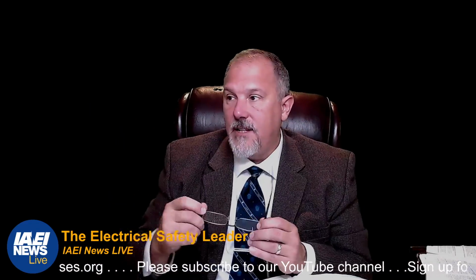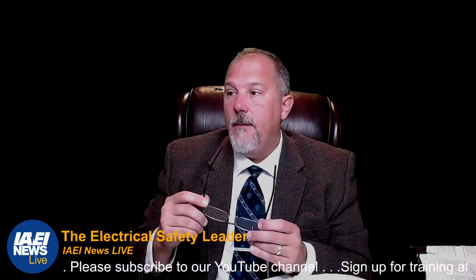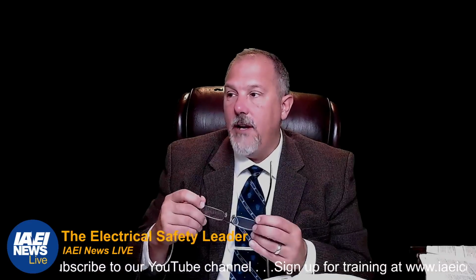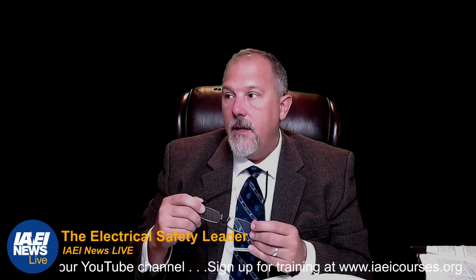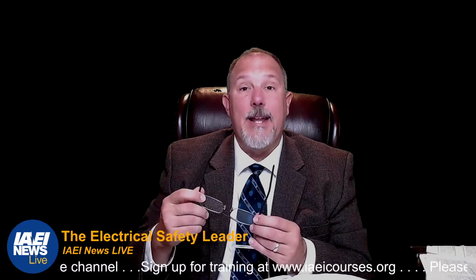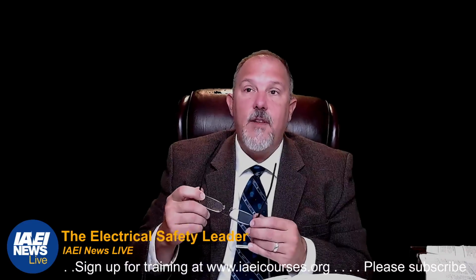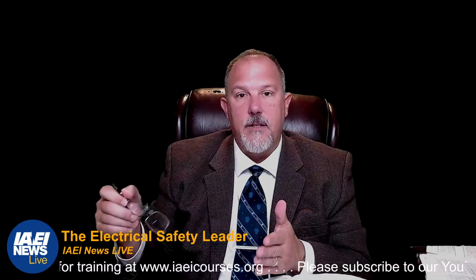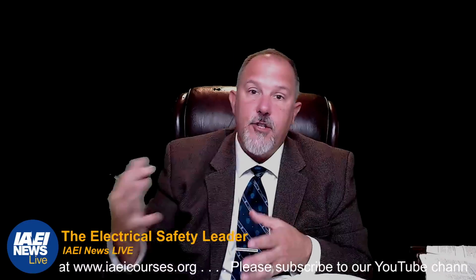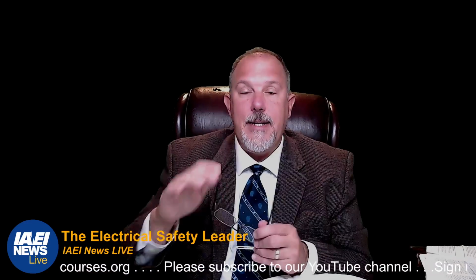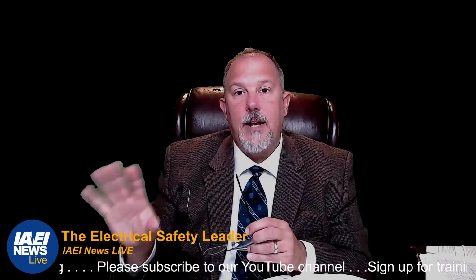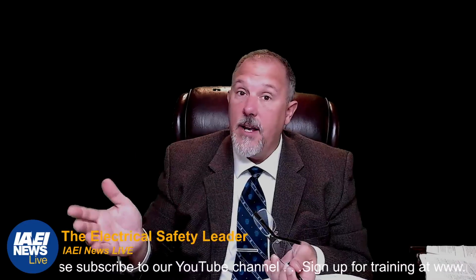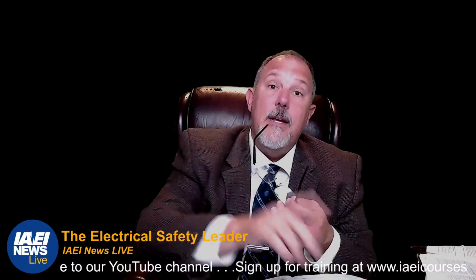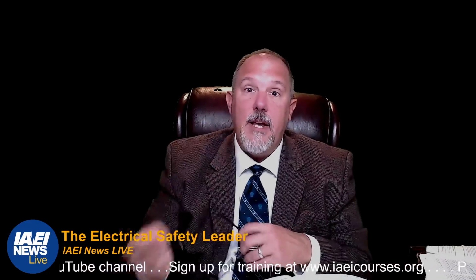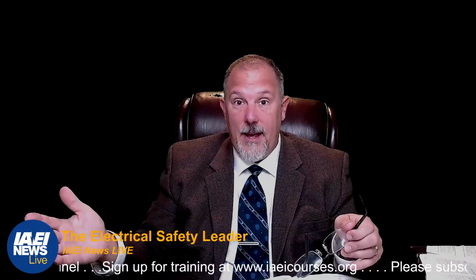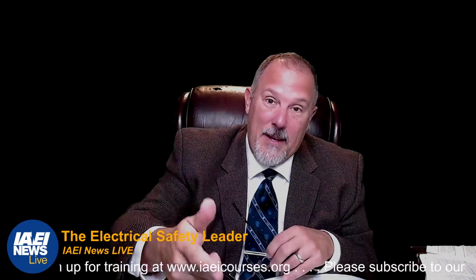Panel boards not listed for the specific enclosure: if the available fault current is greater than 10,000 amps, the completed work shall be field labeled. So what you'll have to do, if the available fault current is greater than 10,000 amps, and you're going to use a retrofit interior, then you're going to need to get an AHJ out there, or a field evaluation body, an FEB, which is defined in the NEC. The FEB and the NEC from the NFPA will get it done ASAP PDQ.